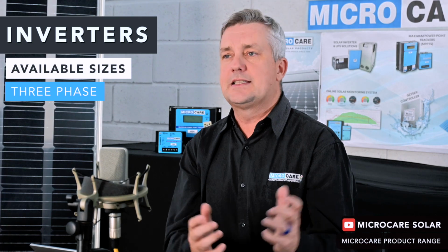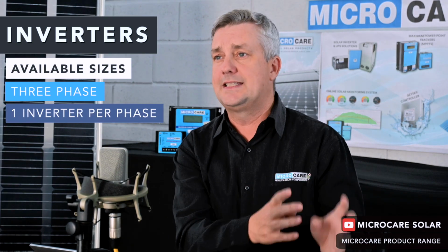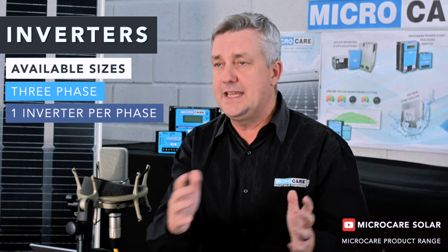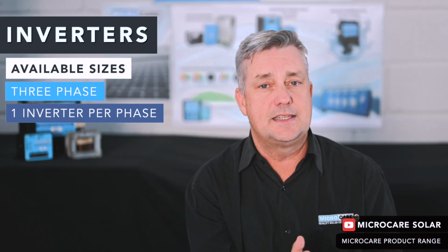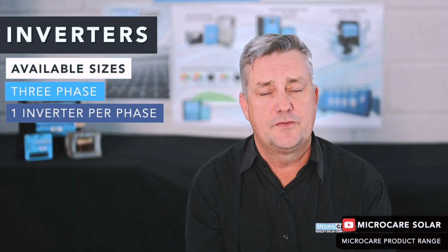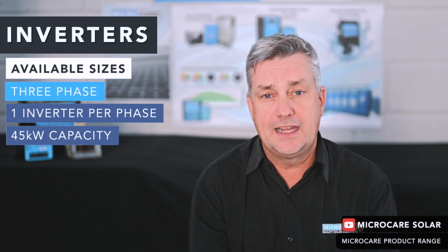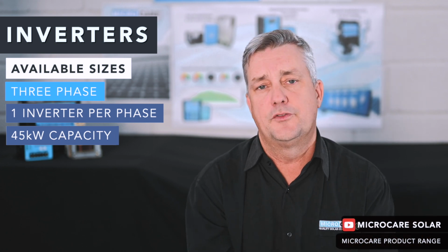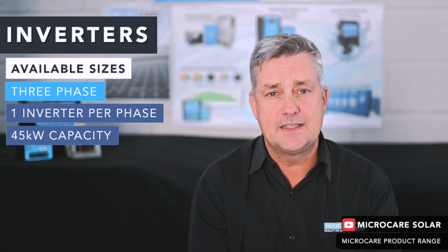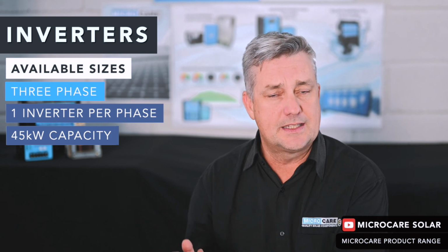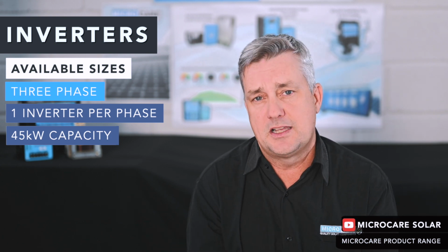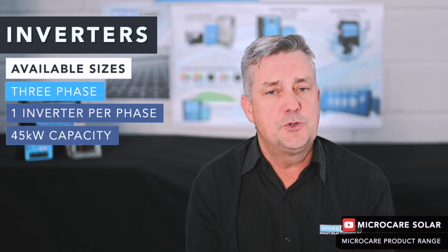If you want to go to 3 phase, you would take any of our inverters, let's say 3 10 kilowatts, and put 1 10 kilowatt per phase, making for 30 kilowatts. Which means our capacity with our standalone items off the shelf here at MICROCARE is 45 kilowatts, 3 15 kilowatt inverters. So when it comes to 3 phase, it's a special application, and the 3 inverters will need to be customized here at the factory. Beyond that, you'll be looking at the MICROCARE mini grid system.